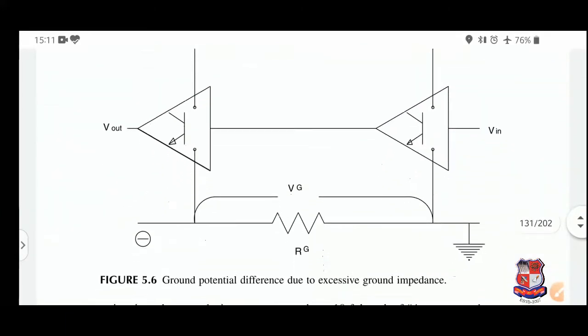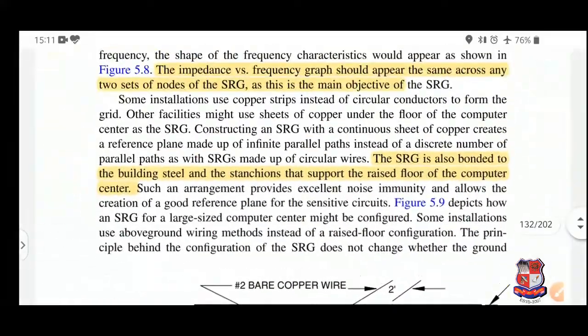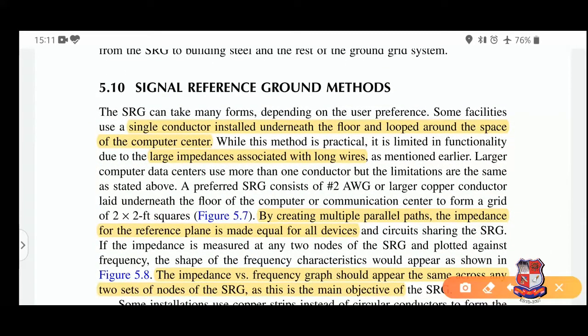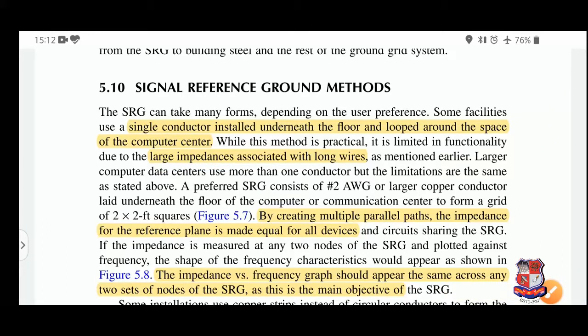Now let us look at the signal reference ground method — how we can construct the SRG. Normally it is a simple method: a single conductor installed underneath the floor, looped around the space of the computer center. One conductor is buried under the floor and connected around the whole computer area via loop wires. One problem is that as the length of this conductor increases, impedance increases, since R = ρL/A. As length increases, resistance increases, again causing noise problems for sensitive equipment.